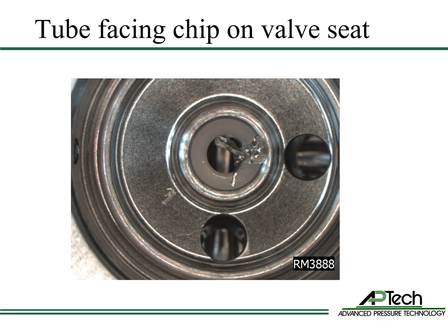Static leak testing failure after piping installation is often caused by stainless chips or shavings from tube-facing operations. In this image, a valve leaked across the seat due to the metal shavings depositing on the seat.